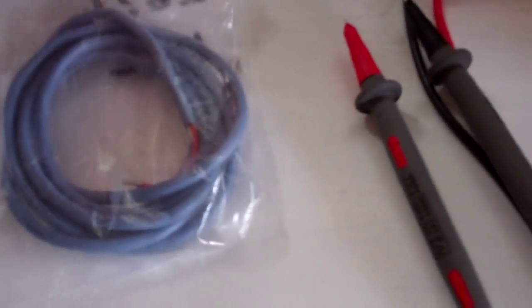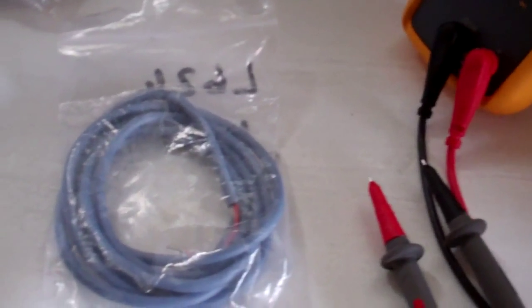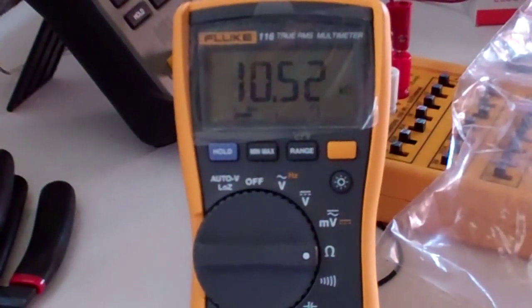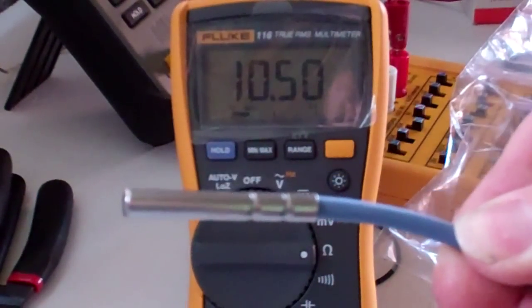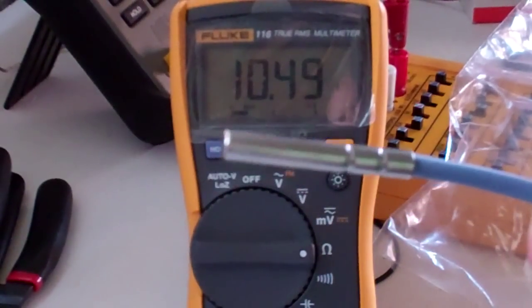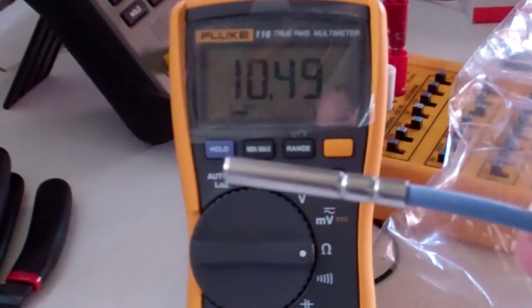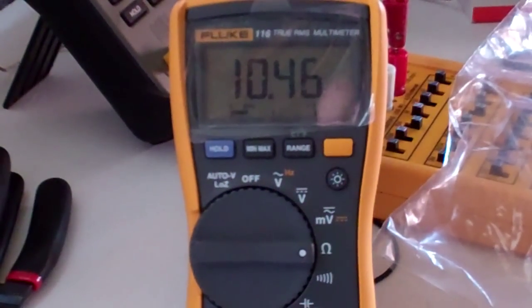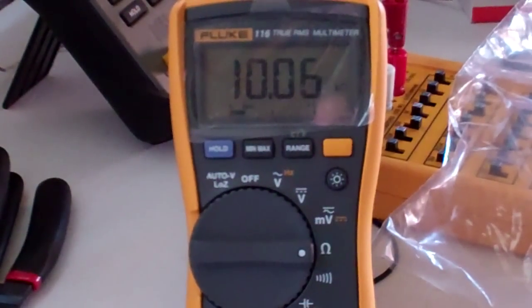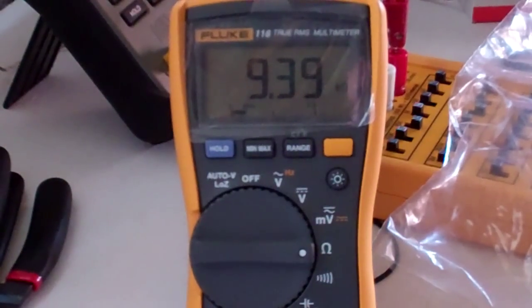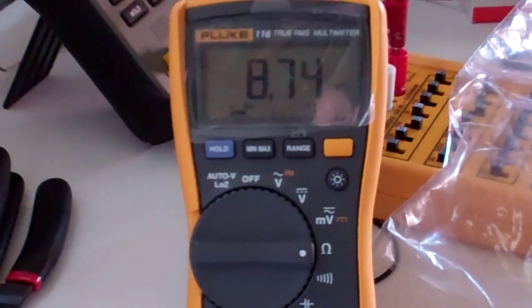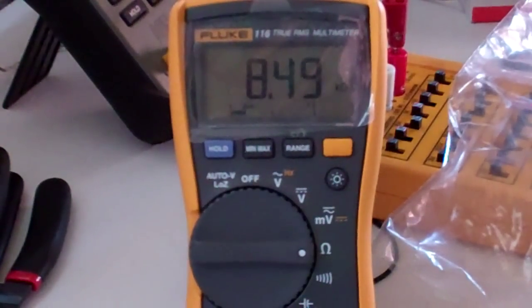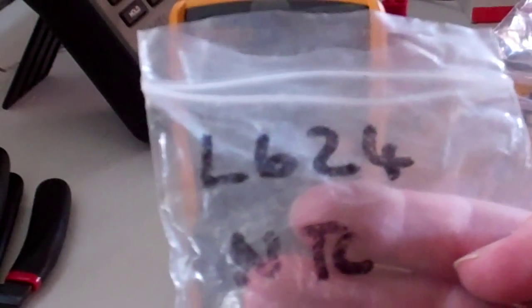That's an NTC probe. This Eliwell probe but it's all pretty similar. That's reading 10.49 kohms and I'm warming it in my hand. So as it's warming up, you can see the resistance is dropping. Which was making an NTC probe and it's come out of a bag with NTC written on it.